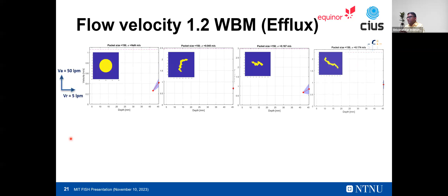So we see that the annular flow doesn't really have that much of an impact on the velocity estimates, either on the mean velocity or on the standard deviation of the estimates for each sample volume. So at least we can say that, within these ranges, the annular velocity has virtually no effect on Doppler estimates. Looking at efflux, when we suck fluid out instead of pumping it in, again for both these conditions we are still able to estimate the efflux velocities quite reasonably.